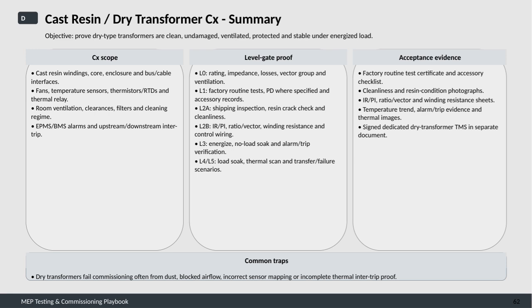The commissioning process is organized into multiple level gates. Level 0 focuses on basic rating, impedance, losses, vector group, and ventilation checks. Level 1 includes factory routine tests and any partial discharge testing where specified, along with accessory records. In levels 2A and B, inspections during shipping for cracks and cleanliness, insulation resistance and polarization index tests, ratio and vector verification, winding resistance, and control wiring are all completed.